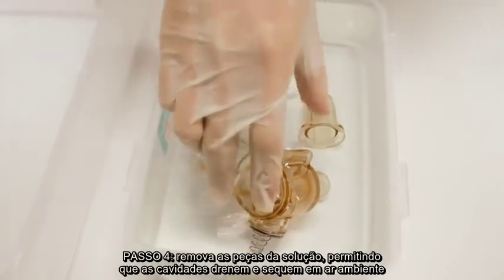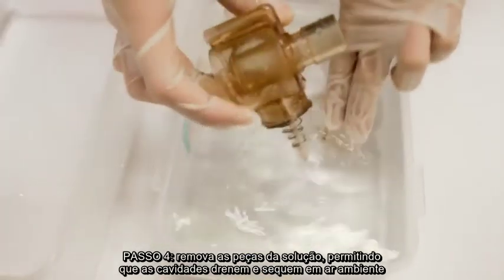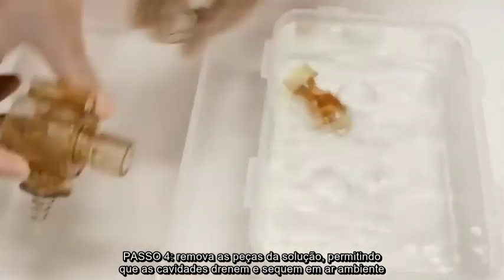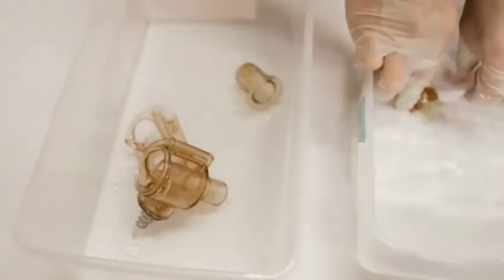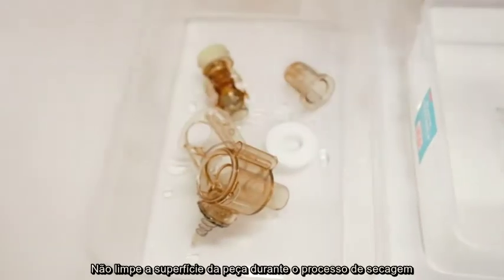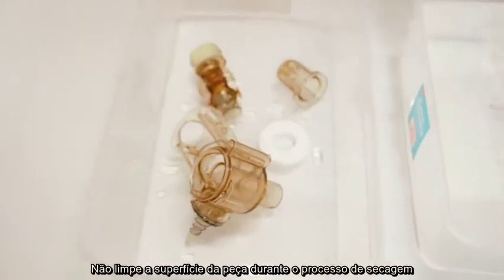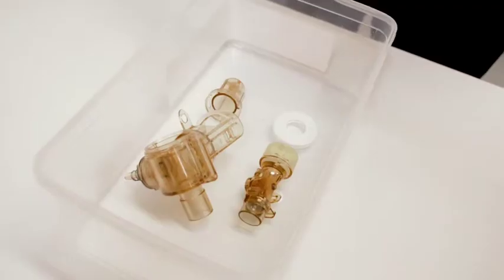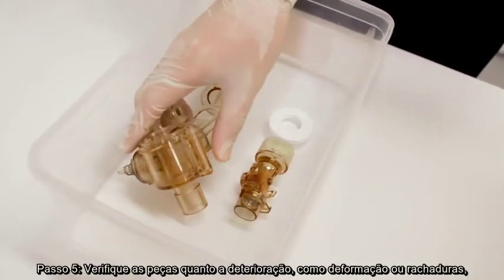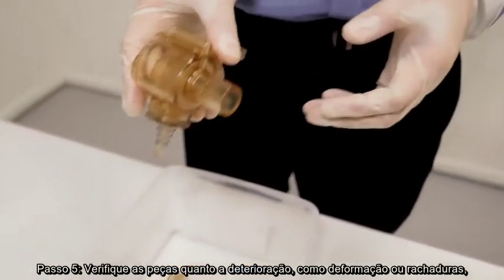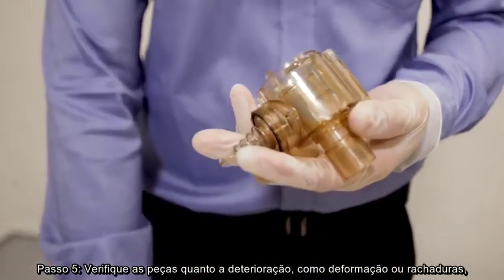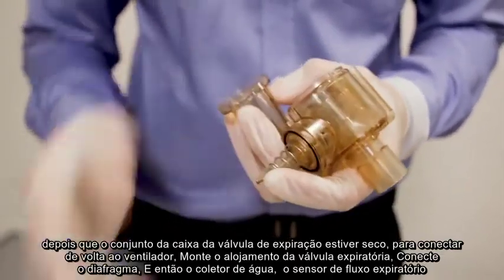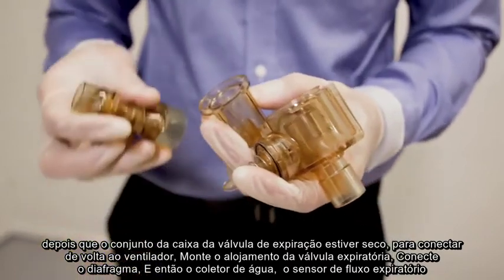Step 4. Remove the parts from the solution, allowing cavities to drain and dry in room air. Do not wipe the parts during the drying process. Step 5. Check the parts for deterioration, such as deformation or cracking, once the exhalation valve housing assembly is dry.